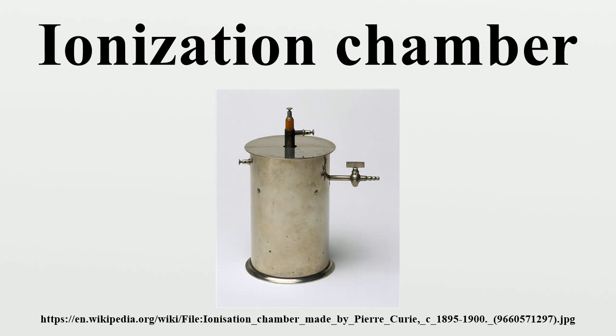Chamber types and construction: The following chamber types are commonly used. Free air chamber: This is a chamber freely open to atmosphere, where the fill gas is ambient air. The domestic smoke detector is a good example of this, where a natural flow of air through the chamber is necessary so that smoke particles can be detected by the change in ion current. Other examples are applications where the ions are created outside the chamber but are carried in by a forced flow of air or gas.